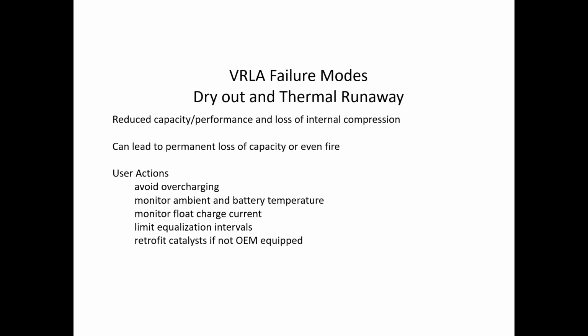I'd mentioned before an amp clamp being a very important tool in your arsenal for maintenance or predictive maintenance of these batteries. You start to see an increase in float current. Usually it's in the magnitude of milliamps per 100 ampere hour. So a 1,000 ampere hour battery is going to draw an amp of float current. You go into a battery room, and you clamp that battery and it's fully charged and you see 5, 6 amps. You know you're on your way to some kind of problem.